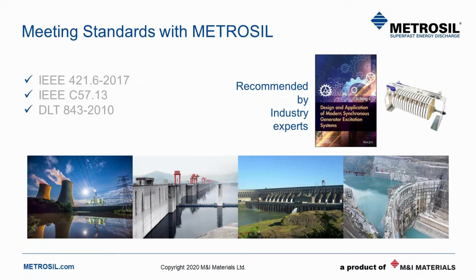Over the years, METROSIL has become synonymous with electrical network protection, and it appears in many IEEE recommended practices and standards. For example, 421.6, a recommended practice for the protection of synchronous machines, C57.13, an instrument transformer protection standard, and DLT 843-2010, a Chinese power industry standard that mandates the use of this protection.